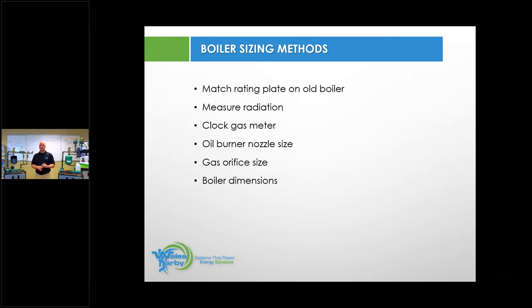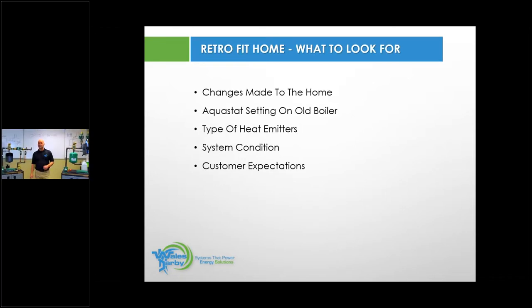We can clock the gas meter, and that will tell us how much gas it burns within an hour or however long you want to clock the meter for. That doesn't size the piece of equipment to the home. We can take the oil burner nozzle out, and it's a 1 gallon nozzle, and the pump's at 100 PSI. That means I will burn 1 gallon if this thing runs for 1 hour straight. That's great, but that doesn't tell you if the boiler is sized correctly to the home. We're making a lot of assumptions there. We can look at the gas orifice. We can go down the line here, the dimension of the boiler. None of that truly tells us what is the right size boiler for the home. So heat load calculation is your best tool.